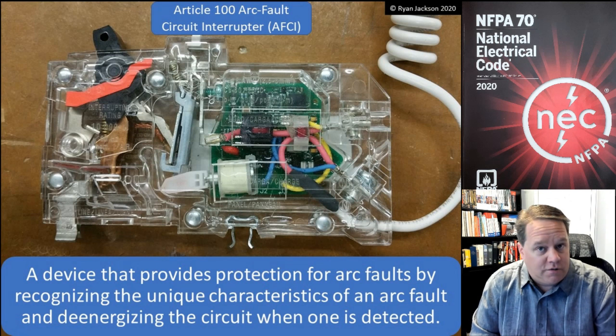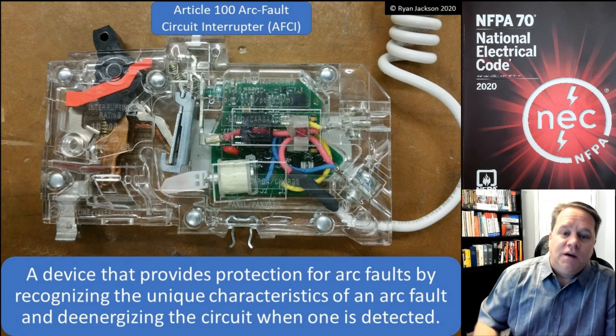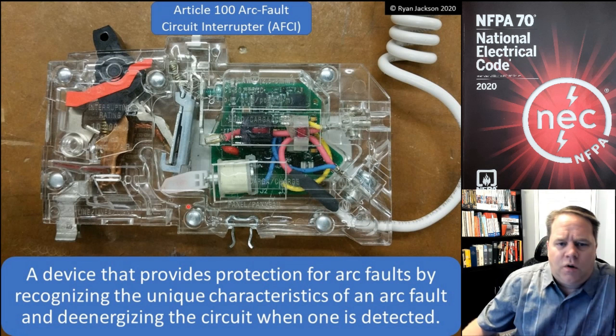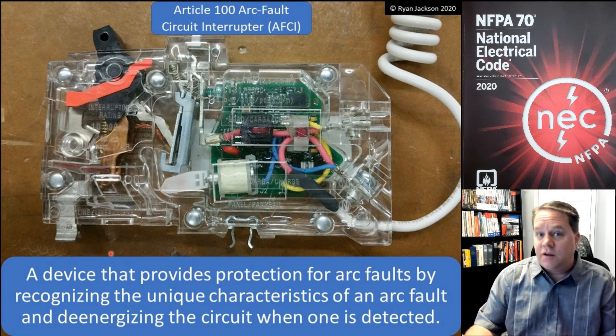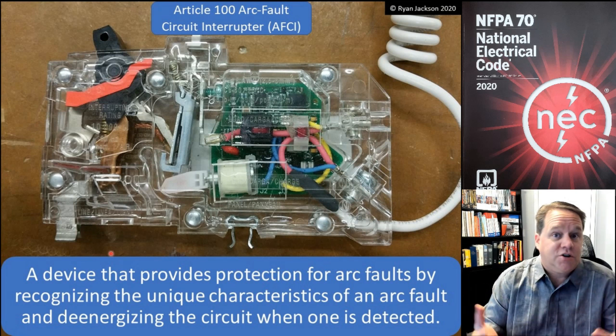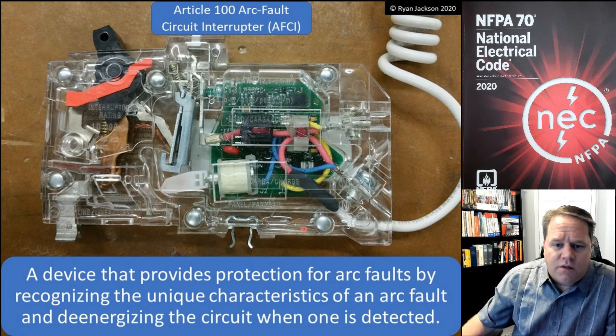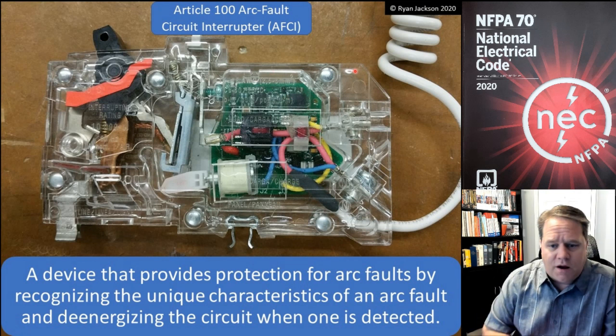Looking at our clear circuit breaker here, everything on the left is just your regular old thermal magnetic circuit breaker that pretty much every molded case circuit breaker is going to have. It's the stuff on the right that makes this an AFCI, and the most obvious part is the circuit board that we can see back there.